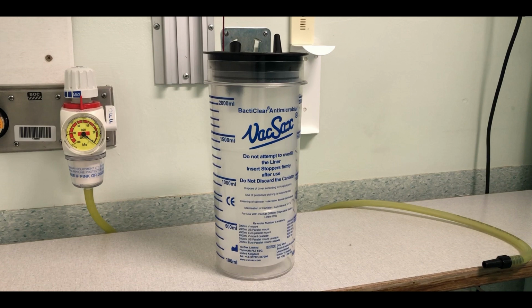Actions to take if there's an error or failure of the device: remove the device from use after ensuring the patient is safe and unharmed. Complete a clinical engineering decontamination form detailing errors, codes or messages. If the device is involved in an incident, ensure the Datix number is recorded on the decontamination form, and then ideally return the device to clinical engineering as it was set up and used. If this is not possible, take an image of the set-up and ensure this is uploaded to the Datix incident form. I would probably just take a photo and then dispose.